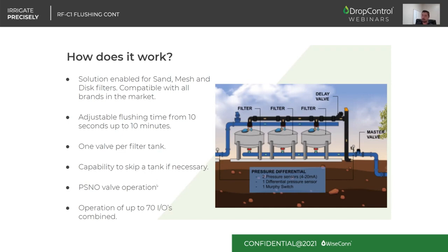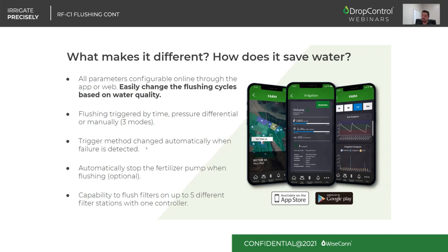The type of valves we are operating on the flushing feature is going to be a pressure sustained, normally open valve. And with the same controller, you can have any sort of combination of up to 70 inputs or outputs. What makes it different? That all the different parameters that are part of the flushing feature can be configurable online through the web browser or the mobile app, meaning that you can change the flushing cycles based on the water quality. We are going to cover some of the parameters that you are capable of modifying remotely, which makes everything a lot easier on the operation side of things.